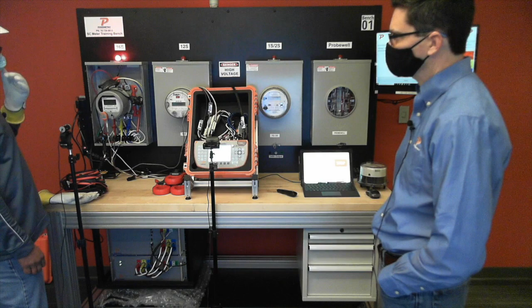So if I had to go out there on a troubleshoot call and realize this meter is out of specification, what steps do I need to follow to safely de-energize and remove the meter? The first thing I'm going to do is talk to the customer and see if I can, again, follow your utility recommendations. But if your company will let you remove the meter under load, you can use your bypass handle and remove the meter. Yep, that's the most important thing.